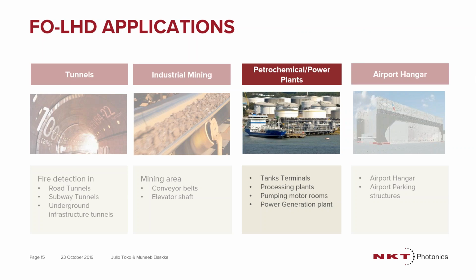My name is Giulio Tocco, so I'm going to continue the presentation, as Munib pointed out some applications already. Some of the applications of fiber optic linear heat detection in general is the ability to do installation in power plants or petrochemical plants, areas that require some more, let's say, unconventional spacings and assets. One example would be tank terminals, processing plants, areas where you're doing fire detection, but at the same time you have a generator or a motor that's generating heat. These are some of the applications that we see for the fiber optic linear heat detection system.